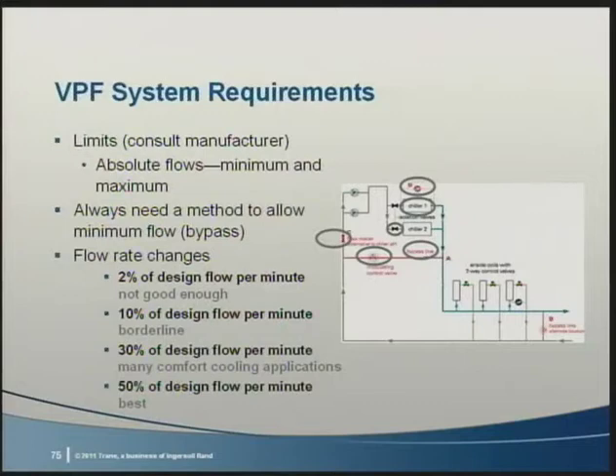First, remember to keep the flow rate between the minimum and maximum flow rates allowed by the chiller manufacturer for the installed chiller. Next, make sure the minimum flow rate can always be maintained. And third, make sure that the flow rate changes are within those allowed by the chiller unit control. Bonnie will address this more in a few minutes.